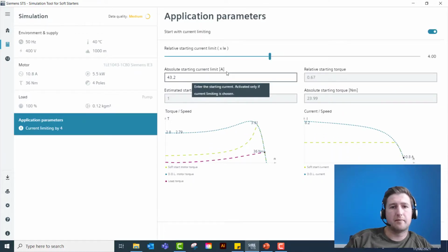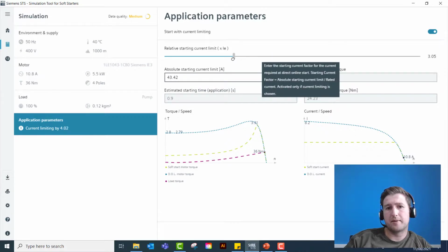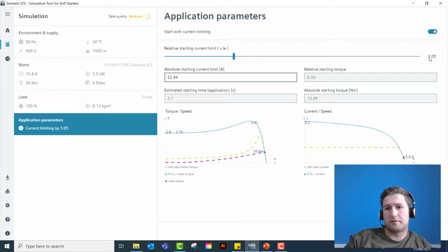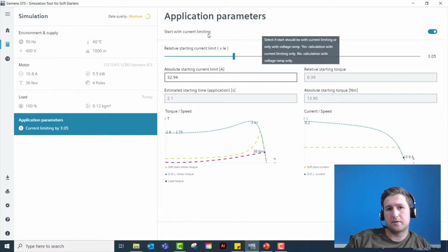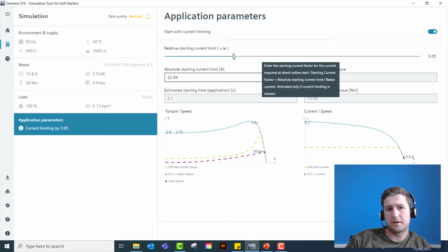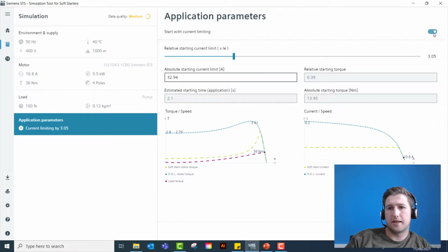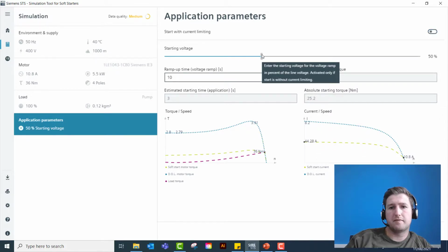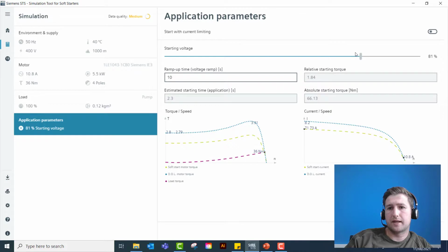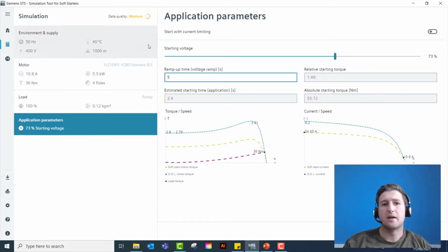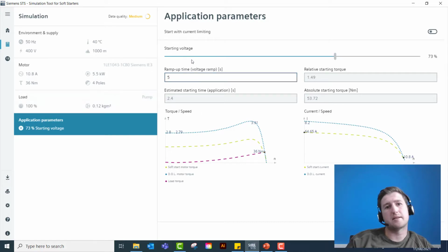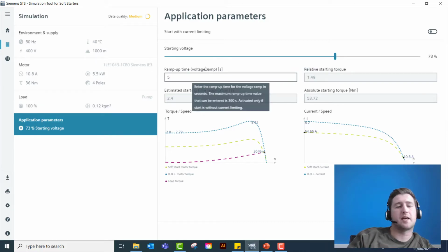And then we can say, right, okay, what do we need to set these parameters to? Well, we know we can set the parameter to 3 times the rated current here, if we wanted. That's the starting current limitation function, so the current limit function can be set to 3. We'll turn that off. What can we set the starting voltage to? Well, we know we can get away with setting it at 70%, and the ramp up time we can set to 5. So what we're doing here is simulating the application and gaining an understanding of the application parameters before we've even purchased the unit.